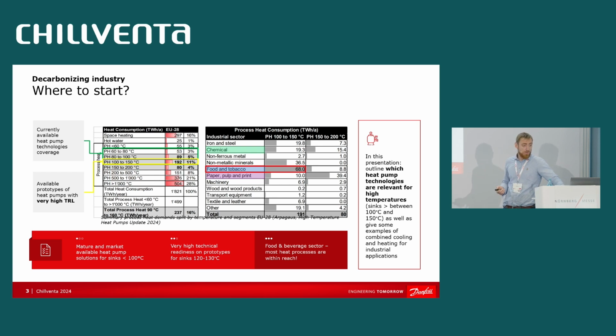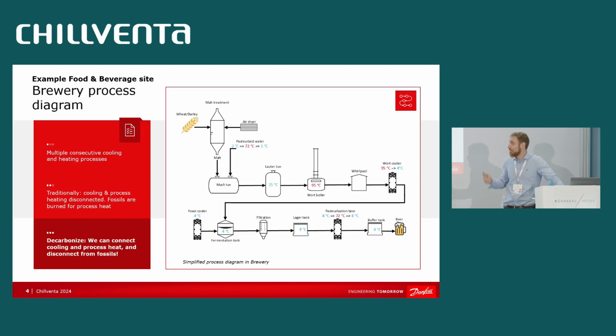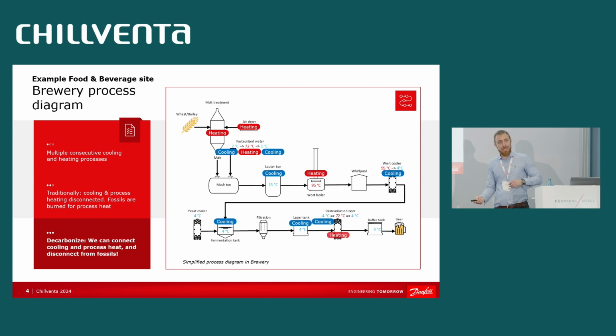largest potential. One of the examples which I found very relevant for being in Bavaria is brewery. Why? Well, I'm not an expert at all, besides being an end user of beer, but there is a lot of consecutive cooling and heating. So you cool down stuff, then you heat it up, then you cool it down again, then you heat it up. Usually you would use a refrigeration system to cool it and a fossil boiler to heat it up. However, you can get rid of the fossil burner, or at least substantially decrease the use of it, and combine cooling and heating. But it's a bit more complex than this.